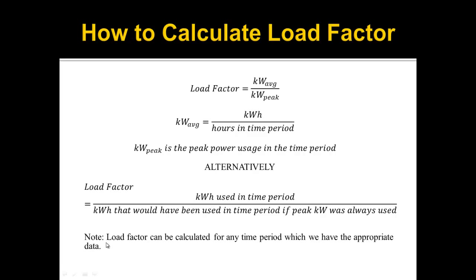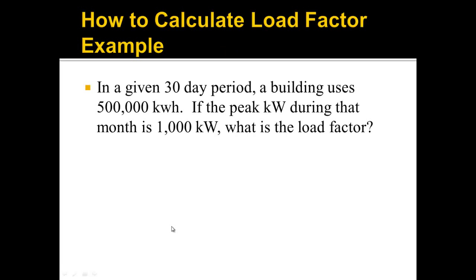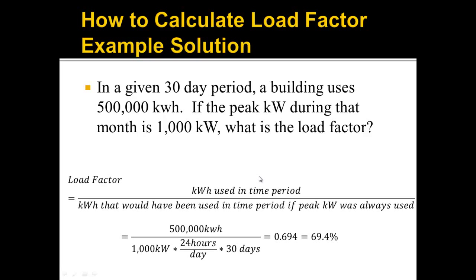Alternatively, you can think about load factor as the kilowatt hours used in the time period divided by the kilowatt hours that would have been used if peak kilowatts was always used. These two formulas give the exact same answer — just two different ways to think about it. Load factor can be calculated for any time period for which we have appropriate data: daily, weekly, or monthly. Example: in a 30-day period, a building uses 500,000 kilowatt hours. The peak kilowatt during that month is 1,000 kilowatts. Using the formula: 500,000 kWh divided by (1,000 kW × 24 hours × 30 days) = 0.694, or 69.4% load factor.